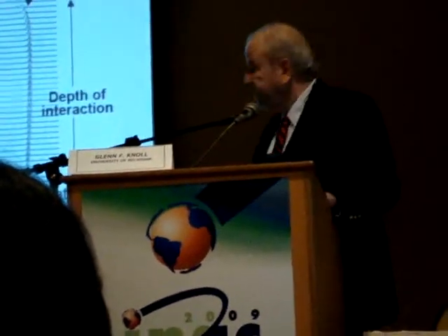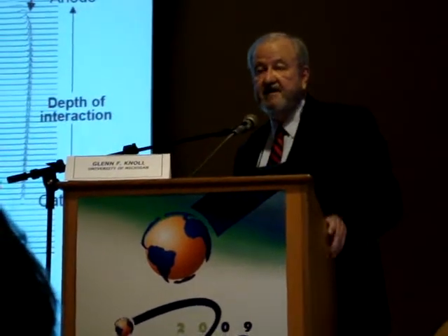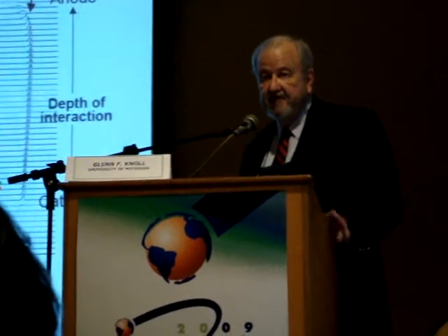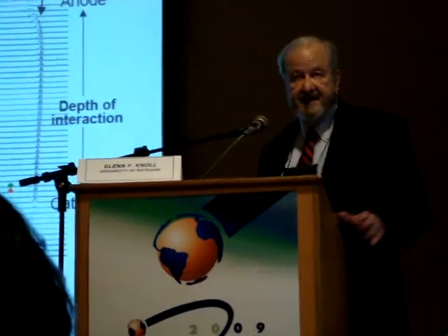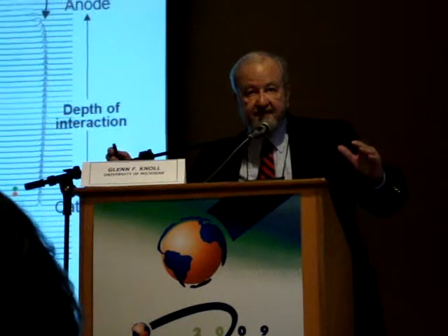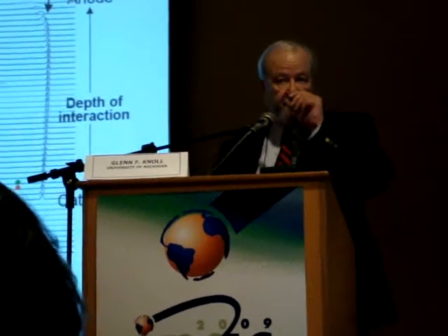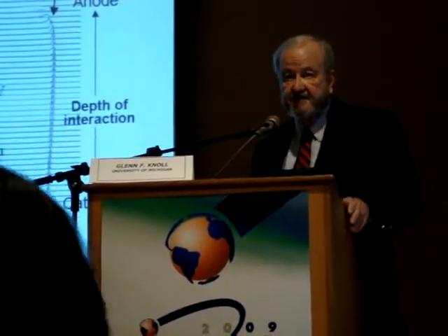When the event occurs far from the collecting anode over here somewhere, you get a smaller average pulse than when the event occurred here nearer the anode, and so there's a shorter drift distance. Well, if you did nothing about this, this is now an imperfection in the detector that will spread out the full energy peak, and it will destroy the energy resolution.